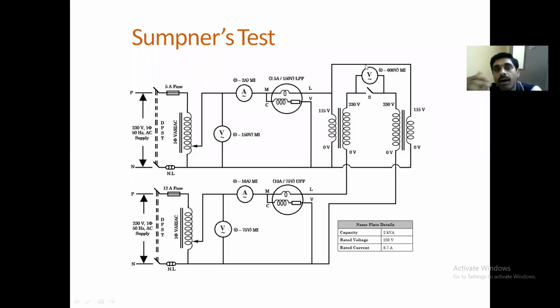But if you take a large transformer, it is uneconomical to connect the full load and conduct the test for finding the temperature rise. That's why it is always better to go ahead with Sumpner's test for large transformers, to measure the temperature rise.